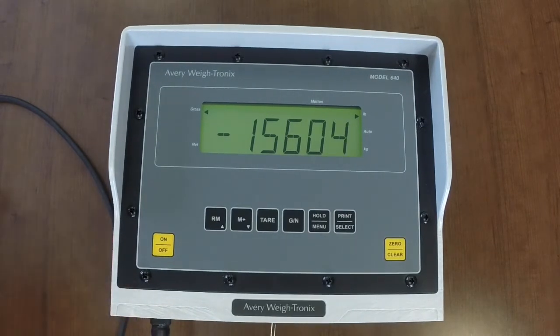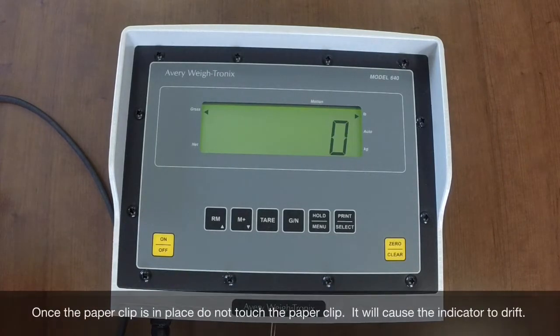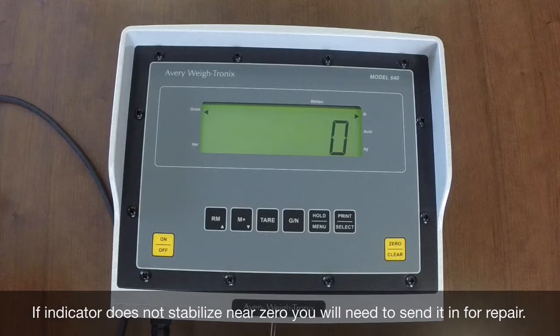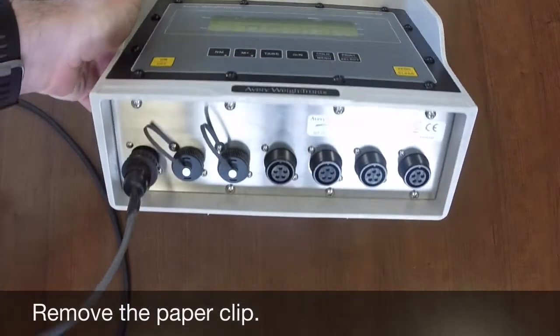Zero the indicator and ensure it stays stable within around 20 pounds. If it doesn't zero or stabilize, contact Scaletech for further troubleshooting guidance or send it in for repair. If the indicator is found to be in good working condition, the next step is to check the weigh bars. Remove the paper clip from the connector at the base of the indicator.